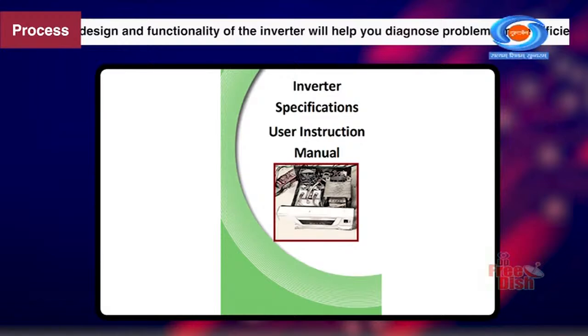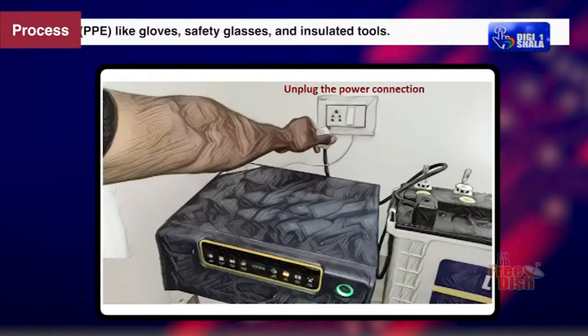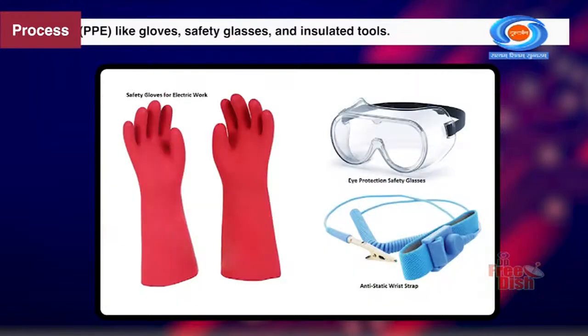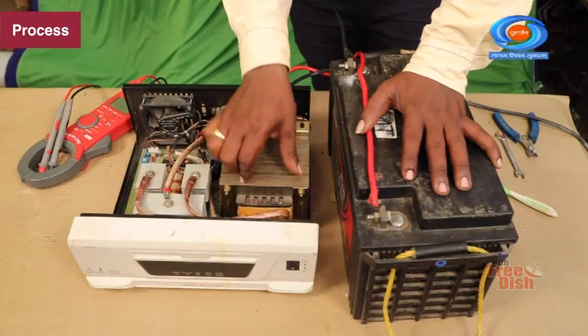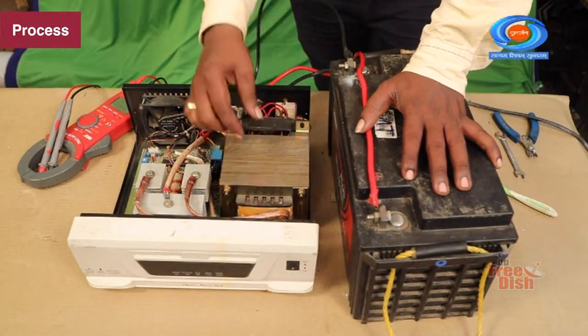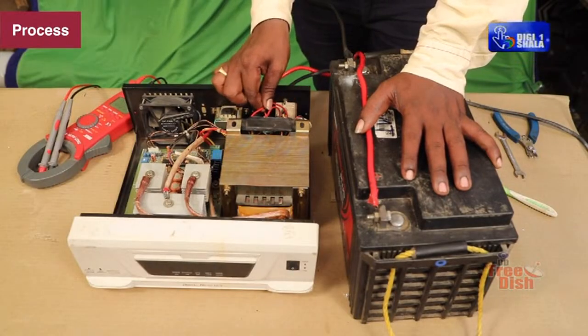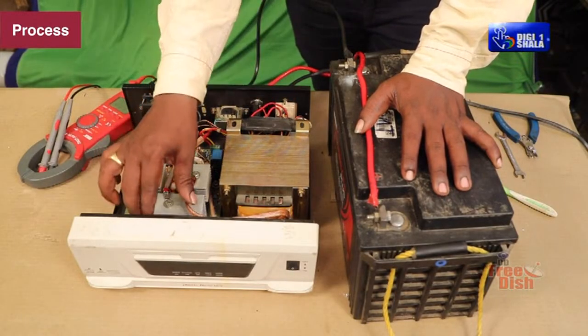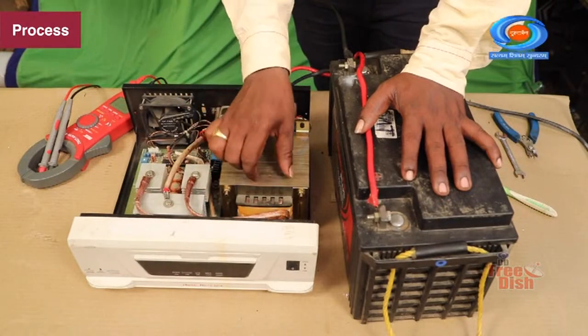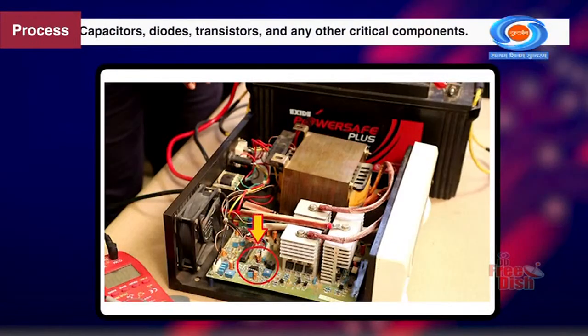Before working on any electrical circuit, ensure your safety by following proper procedures. Make sure the power supply is disconnected and take necessary precautions to avoid electrical shocks. Use appropriate personal protective equipment (PPE) like gloves, safety glasses and insulated tools. Conduct a thorough visual inspection of the inverter circuit and its components. Look for any signs of physical damage, loose connections, burned or melted components or discoloration. Pay close attention to the capacitors, diodes, transistors and any other critical components.